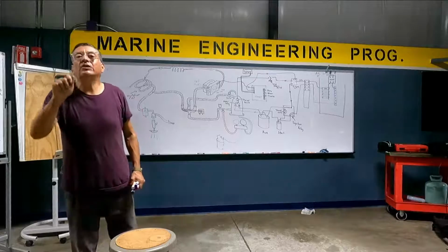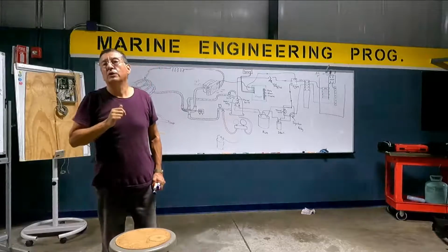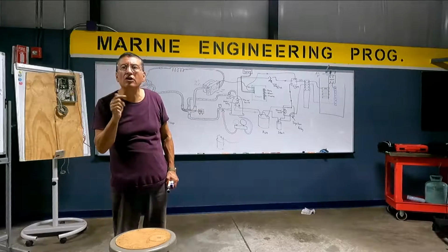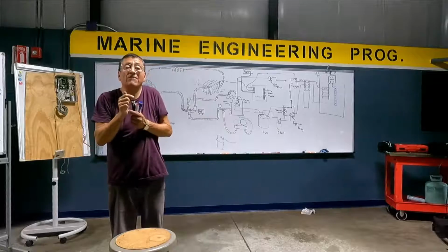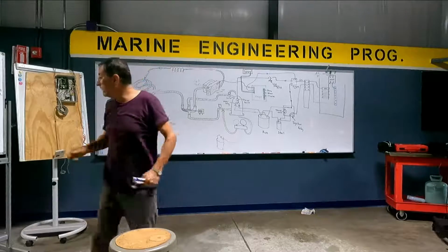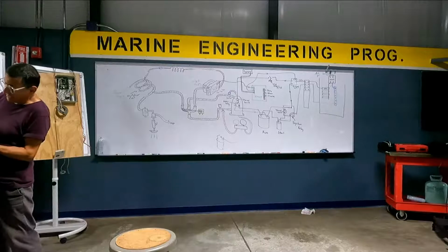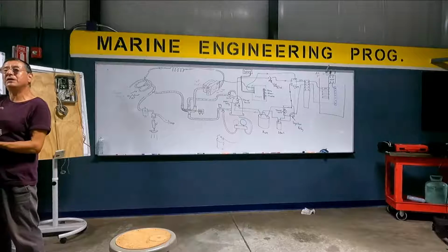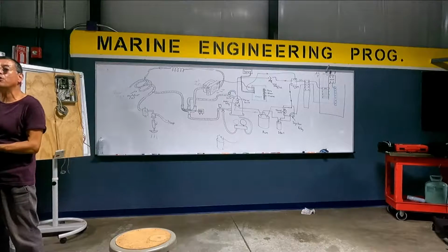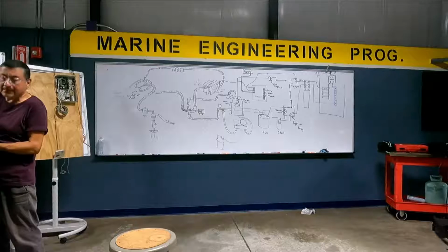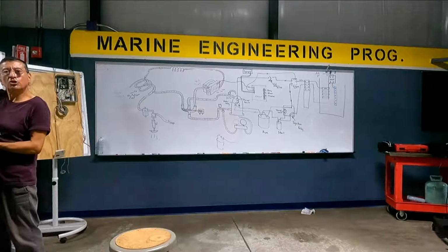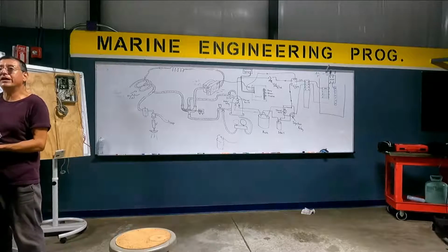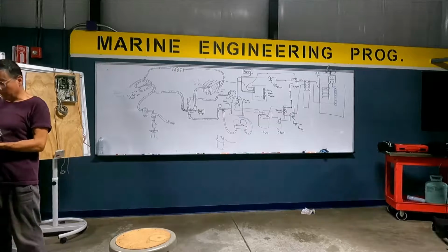Suppose that you select heating mode, and you never hear that click on the solenoid of the Y valve. And of course, the Y valve never operates. You need to verify here what is the signal for the valve. In that signal, the voltage should be between 20 and 30 volts AC. You check neutral and this, nothing. Then that voltage coming from the circuit board is not going out. It's a problem in the circuit board.